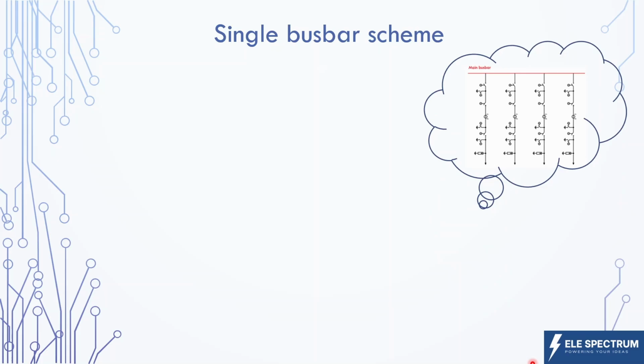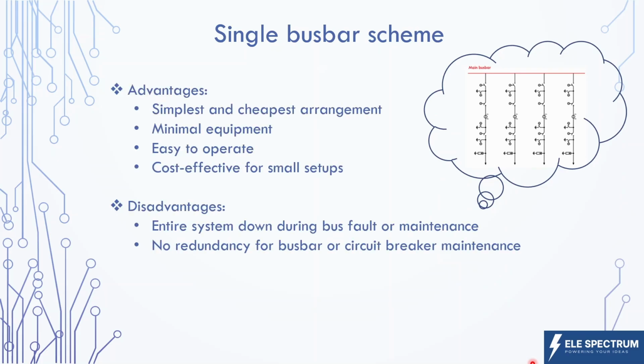Now let's see what the advantages and disadvantages of this bus bar scheme are. Advantages are it is the simplest and cheapest arrangement, minimal equipment, easy to operate, and cost effective for small setups. And when we talk about disadvantages, it is mainly related to the maintainability of the complete scheme. So we don't have any redundancy for bus bar or circuit breaker maintenance. That means suppose we have a fault in this circuit breaker, this complete feeder needs to be taken out, or it is applicable for any of these feeders.